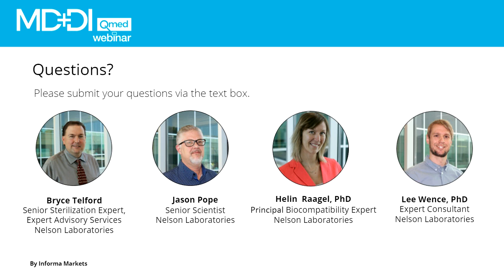Lee, this next question is for you. How is the extraction medium selected, for example, for a flexible catheter? So this is good news. I'm guessing you're asking this question because you've had some nightmares with extractables and leachables with flexible materials. This is a different type of test, where we care more about dissolving and transferring the residues of just the sterilant into the solvent, so water is fine. We don't really care about the material compatibility because we're not trying to extract the device itself, like in an extractables and leachables study. So we use water in our STP, for example. Okay.